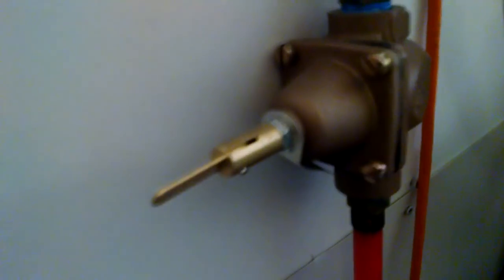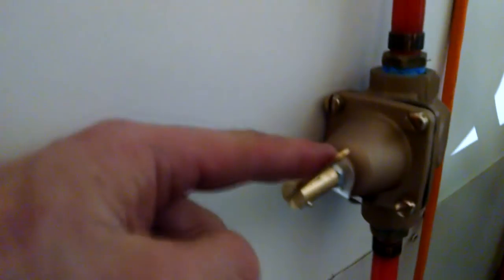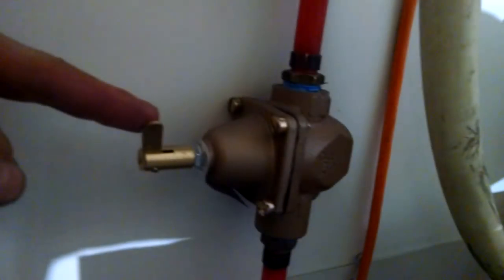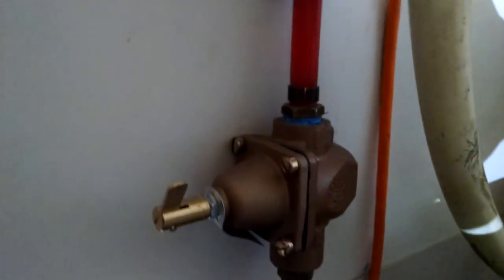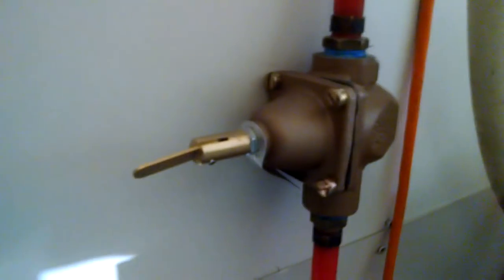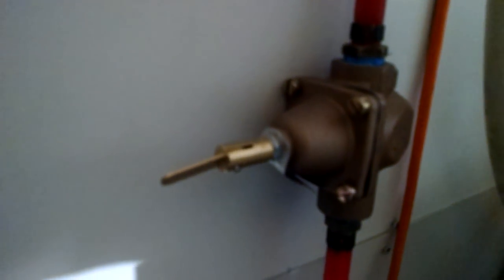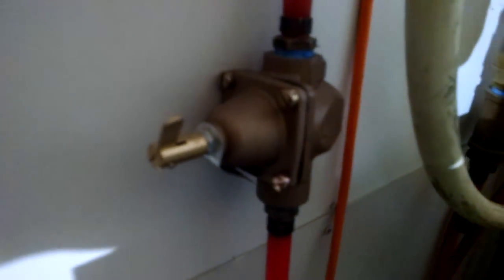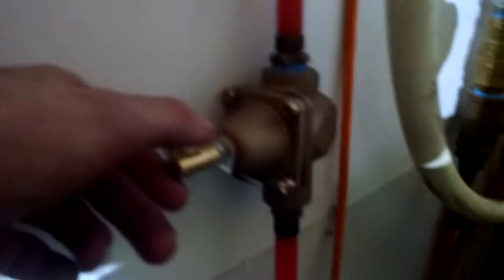What you do is you lift this pin. Normally, when the pin is down, we're at about 12 PSI for the system. When you lift it up, you're filling it with street pressure, or whatever you've got coming in as the supply line here. That's our supply line, which is about 45 PSI.